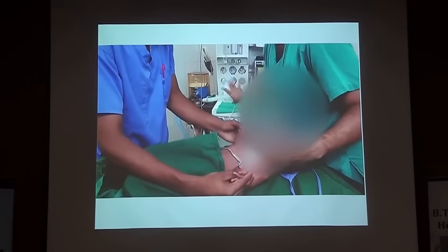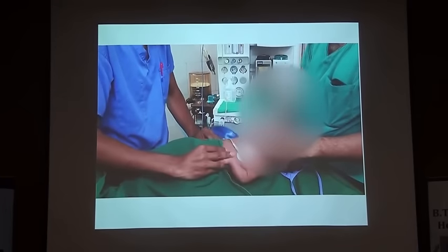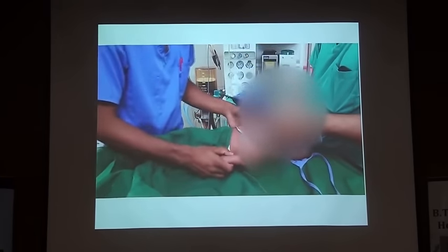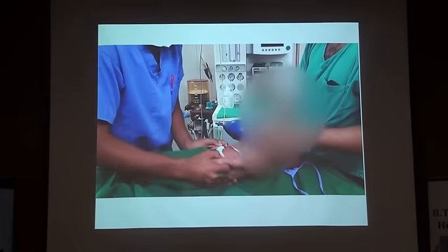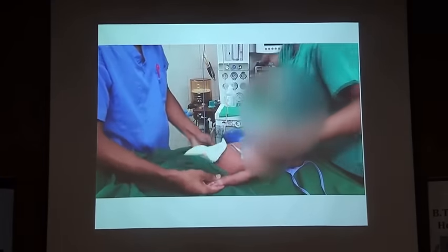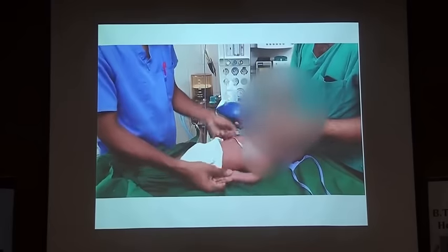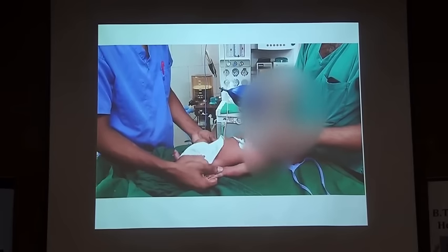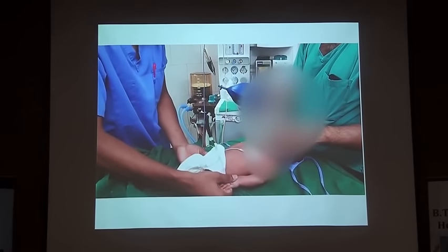We start at around 2 to 3 liters per minute. Here we had air and oxygen available, whereas the previous cases were oxygen and nitrous oxide. Remember, with air and oxygen it takes a longer time to achieve an adequate depth of anesthesia. With nitrous oxide it is always faster, but air has its own advantages. We will not go into the differences between air and nitrous oxide.